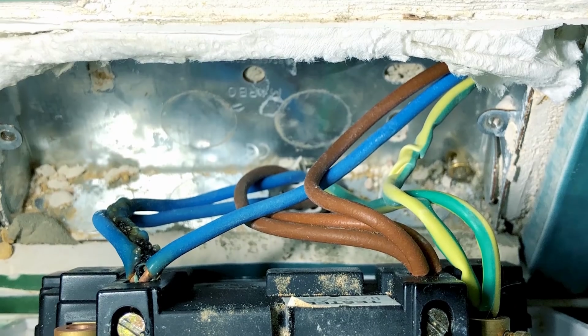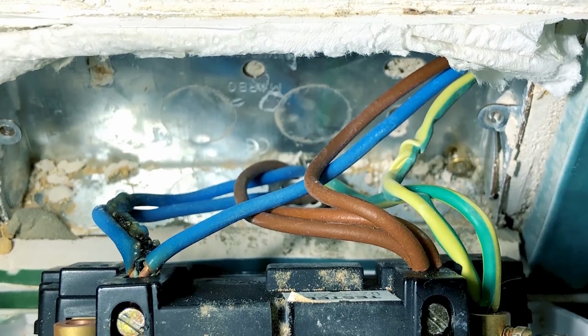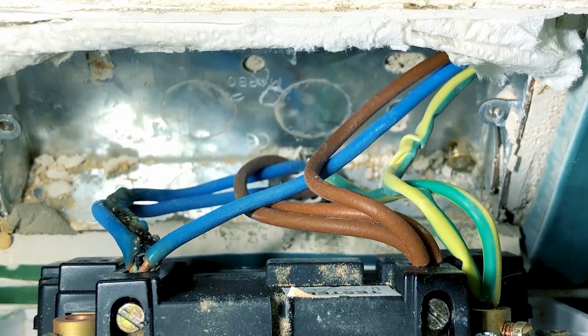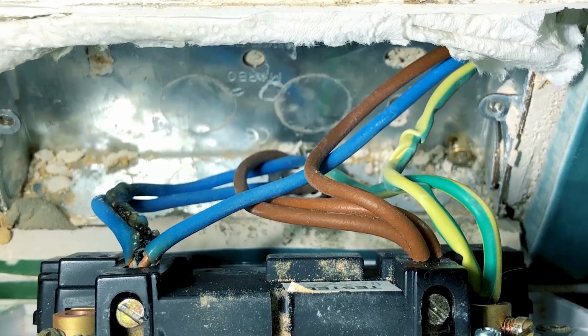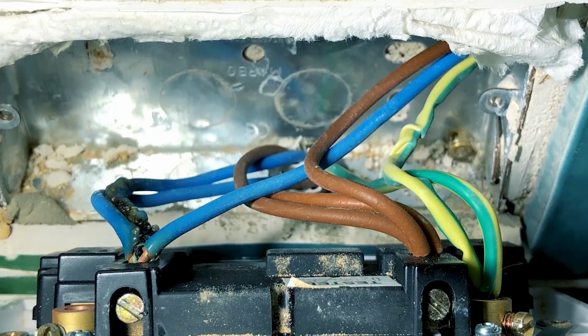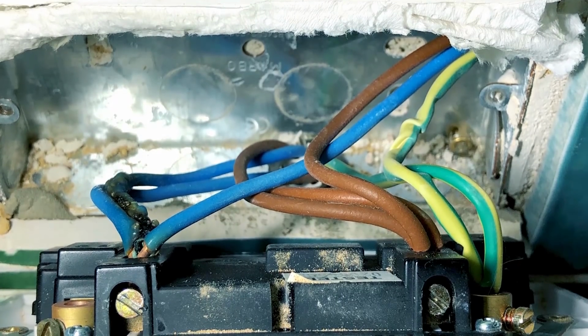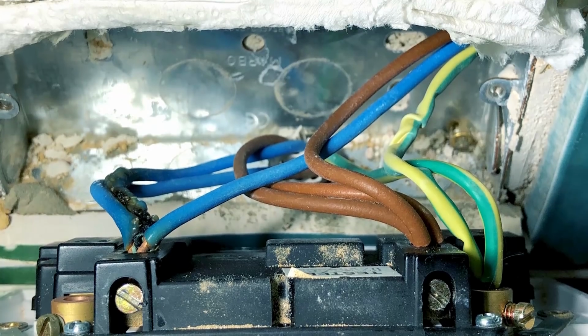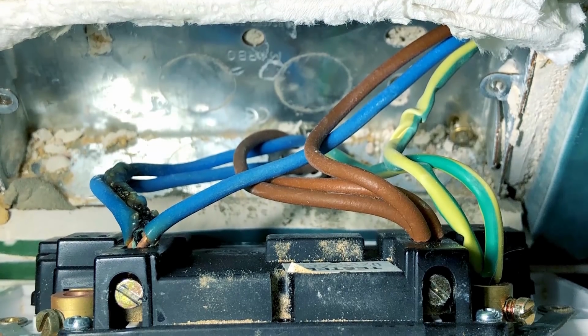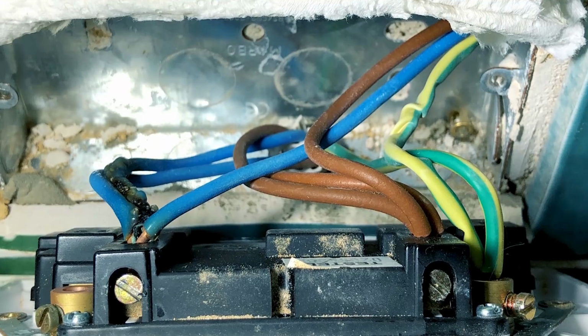Presumably what happened is that because the neutral had busted out of one of the sockets, all of the load was coming down one side of the ring, only on one leg, which meant that leg was overloaded on the neutral conductor, causing the issue.